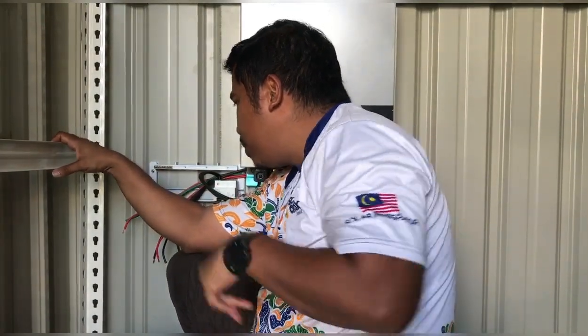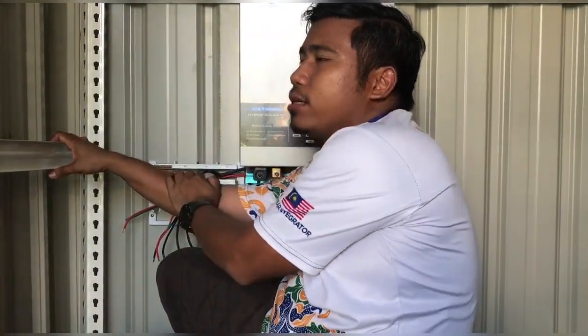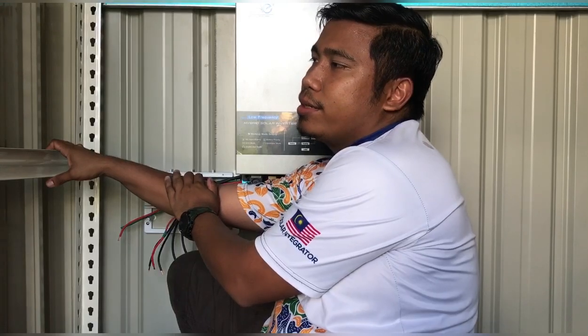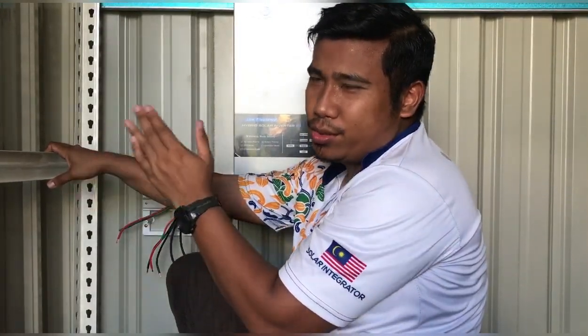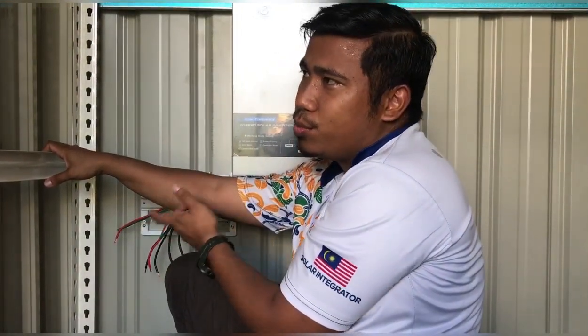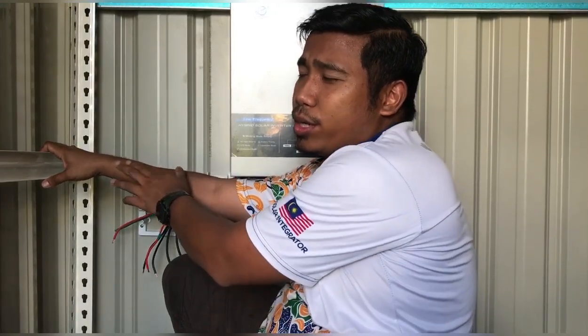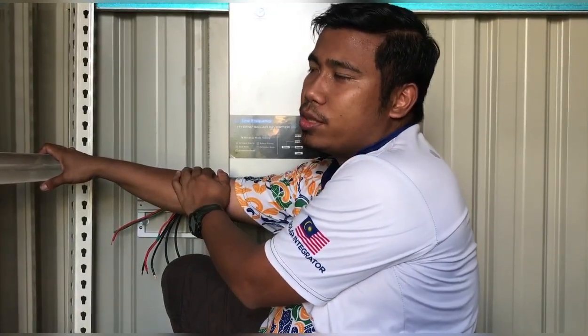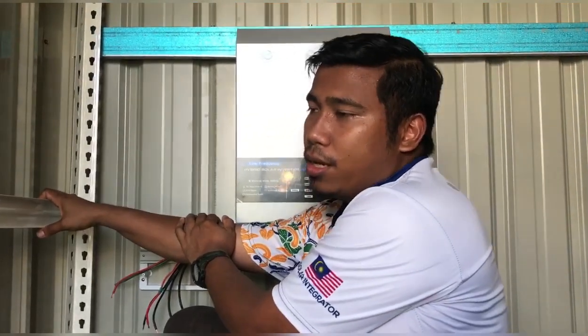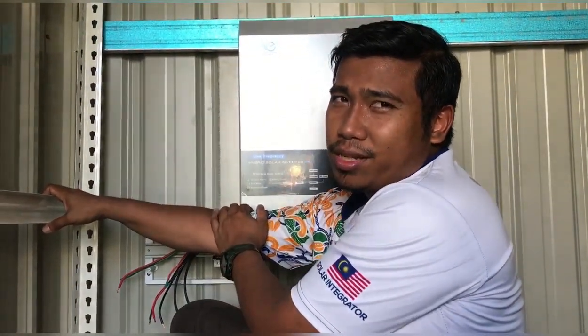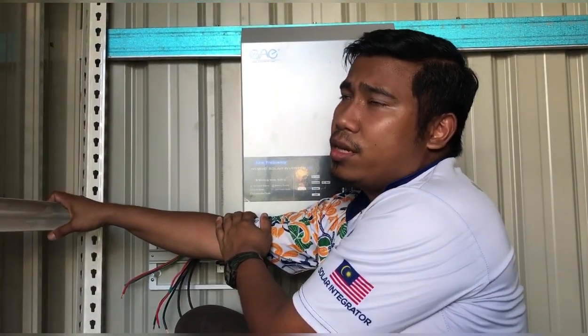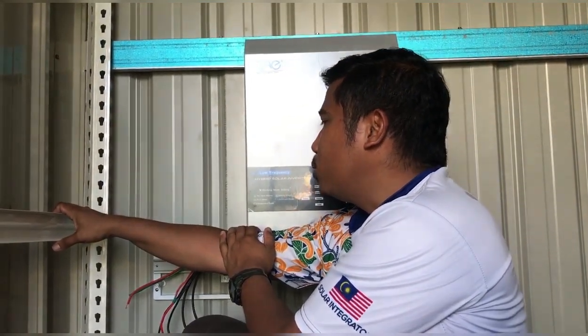After the inverter, you need all sorts of breakers: DC breaker for battery and solar, AC breaker for AC input and output. You might put SPD as well, surge protection device, for the AC side and also for the DC side, especially for the solar panel. That will be it.